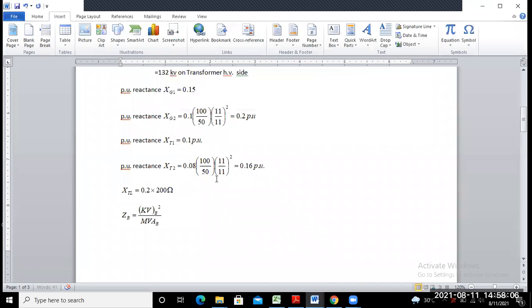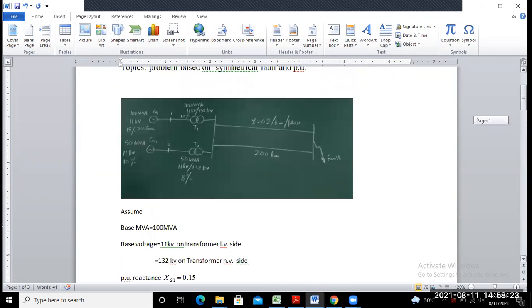But what is the value of base voltage here? Base voltage is how much? We just find out the base impedance on the transformer high voltage side, is it not? Transformer high voltage side. So what is the base voltage rating here? 132, is it not? 132 kilovolt base voltage on the transformer high voltage side.